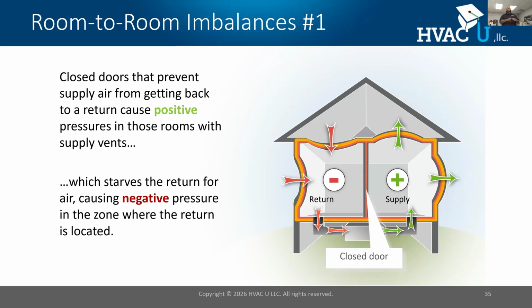In all the rooms, that should be balanced with the exception of the kitchen and bathroom. We don't want return air back. So this is done for bedrooms. And if you see on a picture, if I have an imbalance, that's going to cause some comfort problems, and it can also exaggerate building shell leakage. Okay, so let's discuss the procedure.